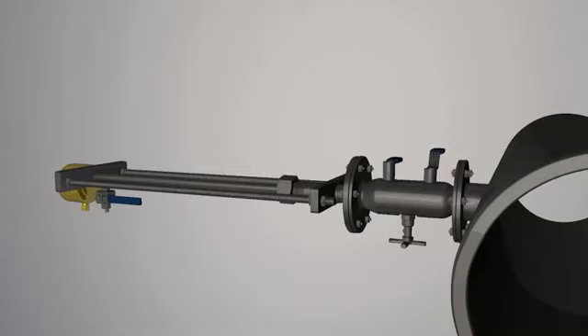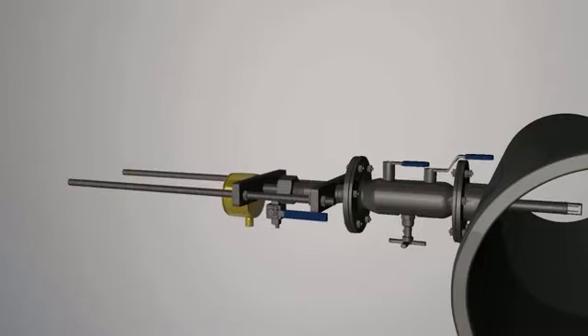This illustration shows how dual insertion rods provided on meters with greater than 50 psig pressure control insertion and retraction of the probe while the process line remains under pressure. The packing gland is tightened.